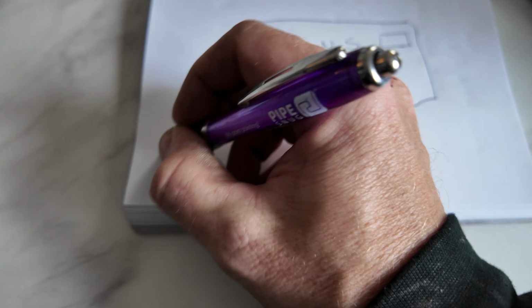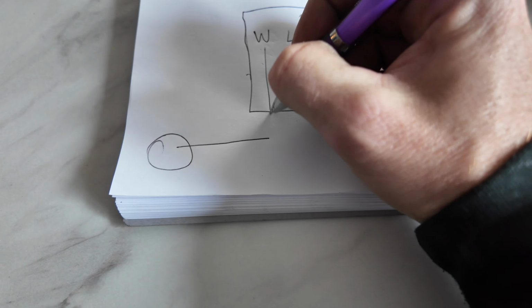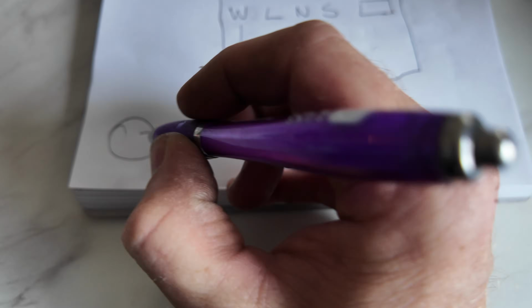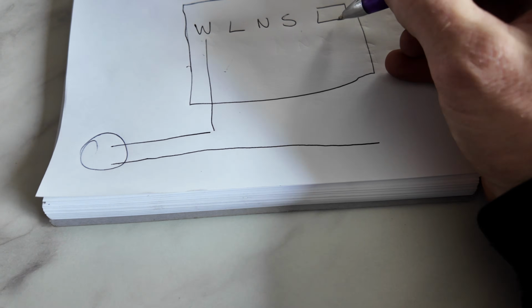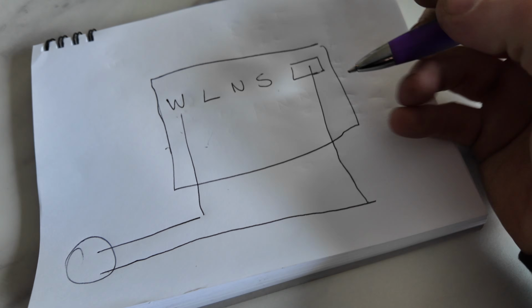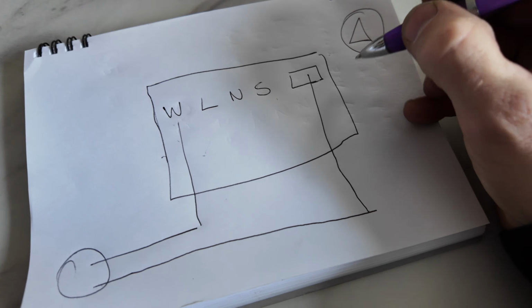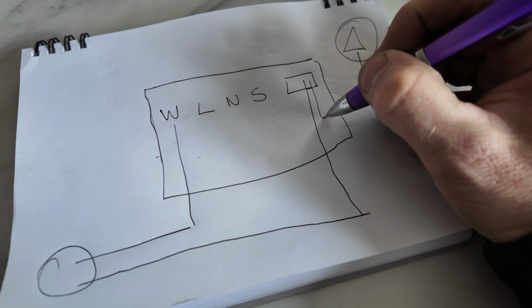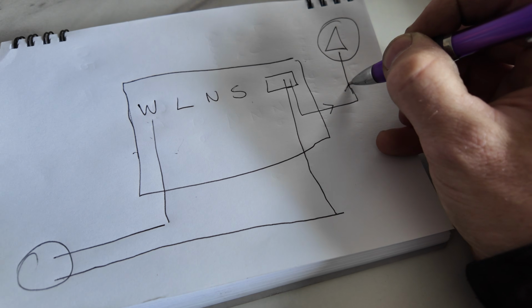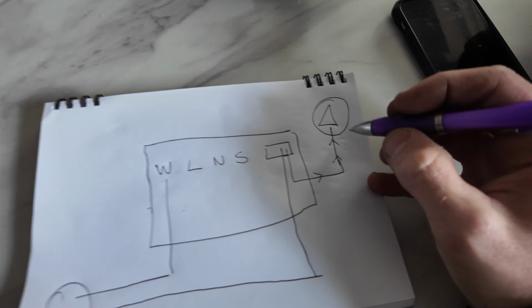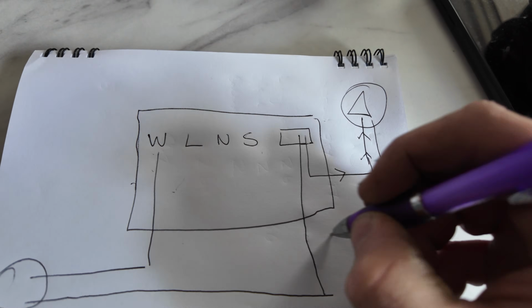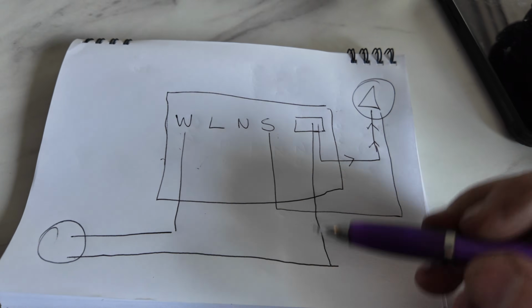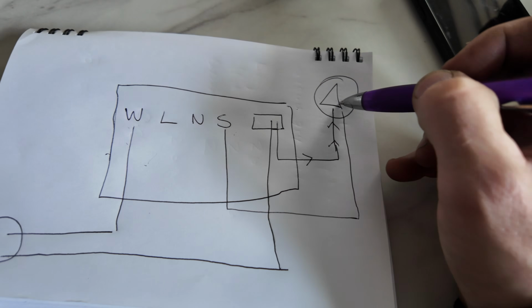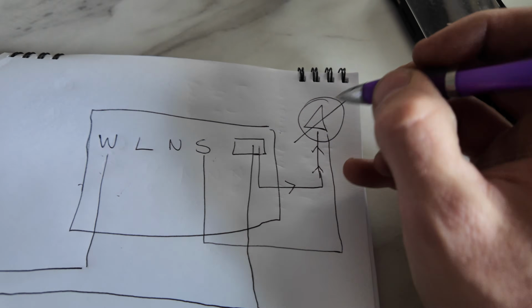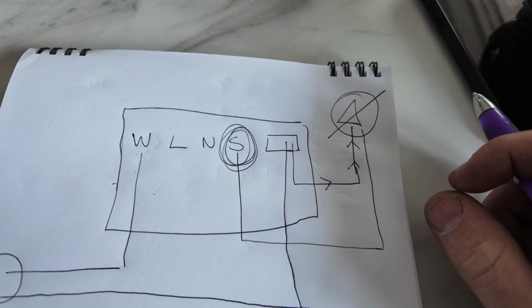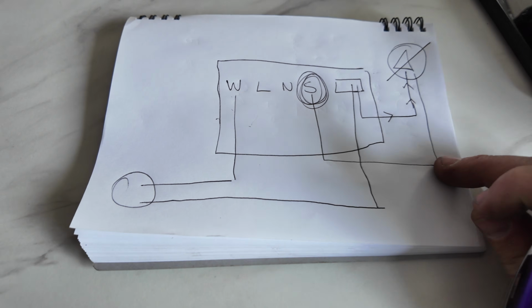So outdoor unit here, right? We've got W going to W, okay? The other one, S, from your outdoor is going into here, the blank. Your condensate pump here, we're going to have connected there, so it's going through like that. Then that from your condensate pump is going to come back through to S. So you can see there, it has to go through the pump to power it. If that pump dies, it'll cut the power to here and it won't work. That's how you wire it in. It's a little bit like a condensate pump for a boiler.